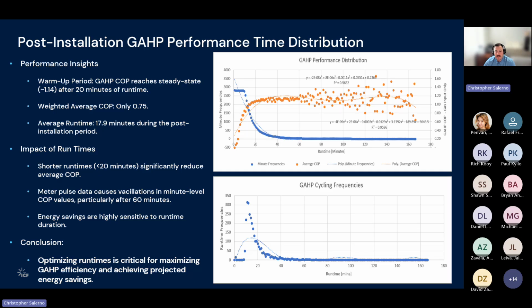The gas pulse meters work in a way that they pulse when a certain amount of volume goes through them. And say that pulse doesn't happen until the next minute, the next data logging minute. So then most of the gas came through the last minute or hour, but then you logged it in the next hour. And so there's a little bit of an offset between that and the net heat output, because the flow meters work in the same fashion, but they're pulsing a lot more. So we have higher resolution of data. So really what we need here is to be able to get more data of these things running more than an hour.